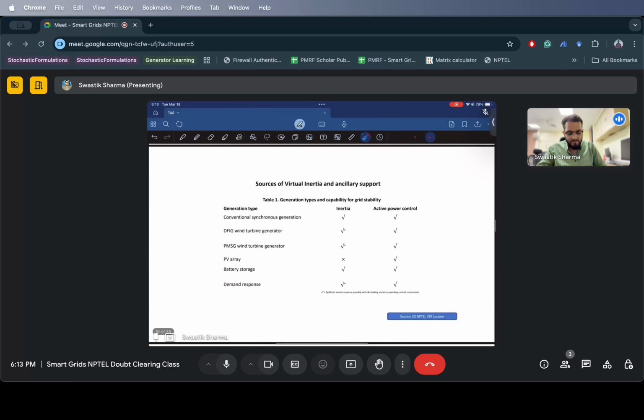So if you see in this table, it tells you for different generating devices, whether you can get inertia or active power control out of it. As you can see, for a conventional synchronous generator, because it has a rotating turbine and rotating mass, you have inertia in it, and you can also control active power by controlling the governor output.